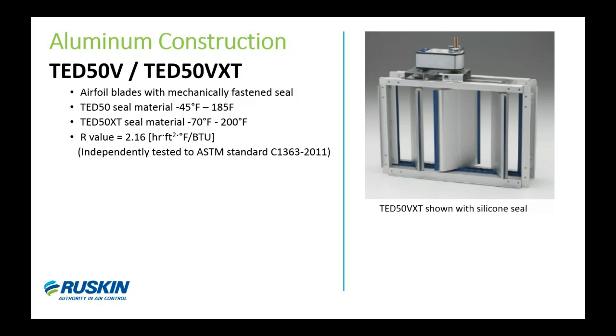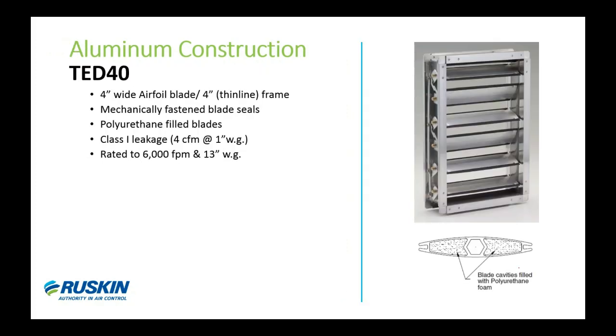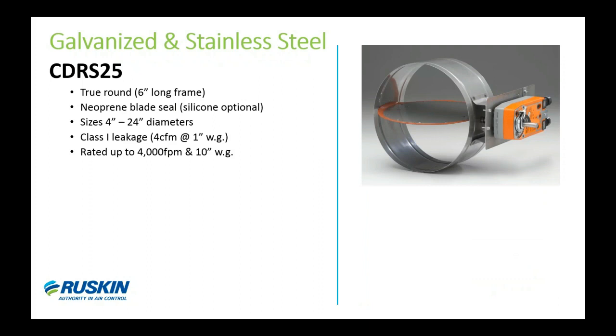While talking about thermally efficient damper models, I'd like to point out a newer economy model known as the TED40, also aluminum construction. This model has a four-inch wide frame with four-inch wide airfoil blades filled with polyurethane foam. The TED40 uses the same Rusca-Crane blade seals, flexible stainless steel jam seals, and polycarbonate bearings as our CD50 and CD60. The TED40 is also being submitted for R-value testing and we hope to have results soon. If you need a damper with higher thermal efficiency than a standard damper but at a lower cost than a TED50, this would be a great choice.